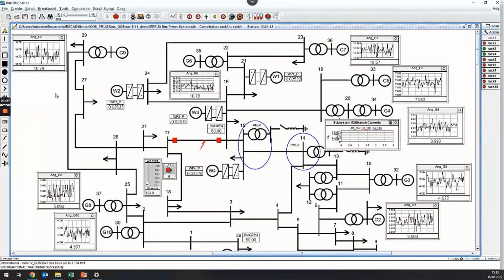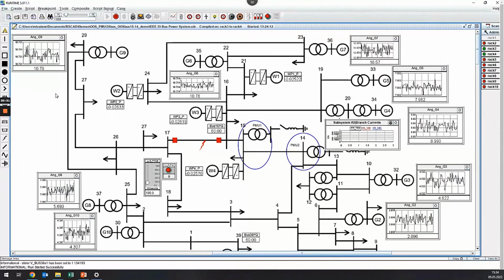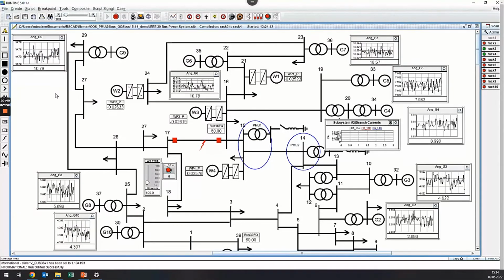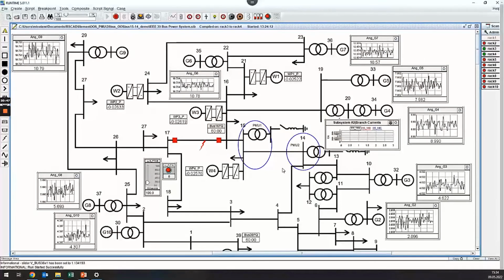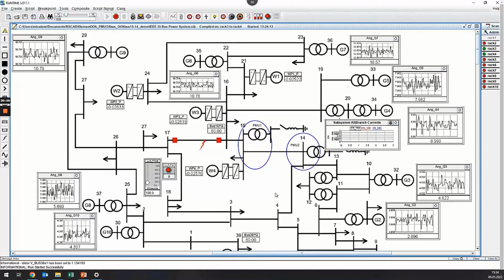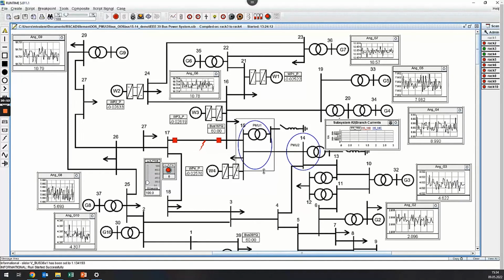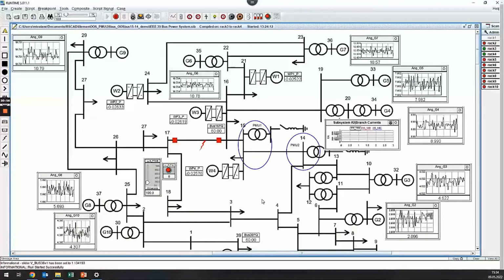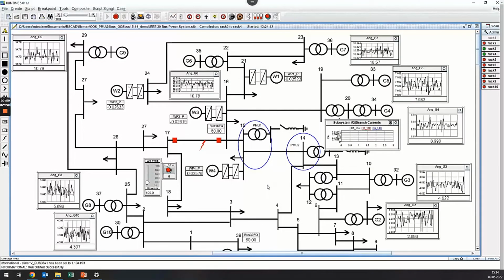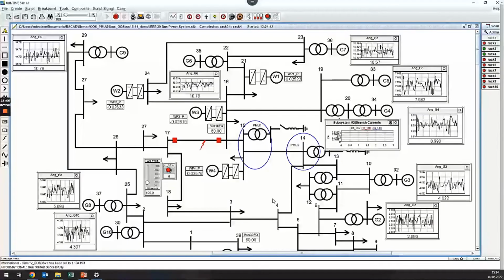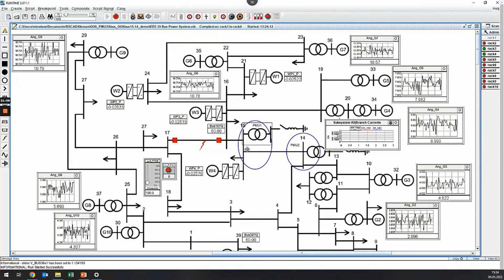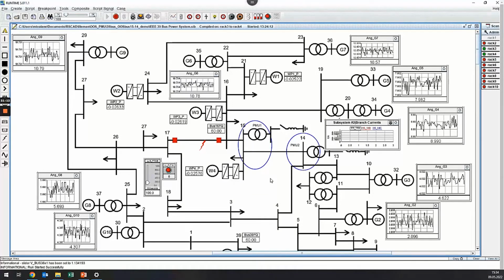We are now in the RTDS runtime environment, and we are running the IEEE 39 bus test network to demonstrate the algorithm's performance and compare it to the impedance-based protection relays. In the network, the protection algorithm is installed on the transmission line between buses 14 and 15 and receives its measurement data from two PMUs located on the buses, respectively PMU 1 for bus 15 and PMU 2 for bus 14. The impedance-based protection relays are located on the bus 15 side of the transmission line.